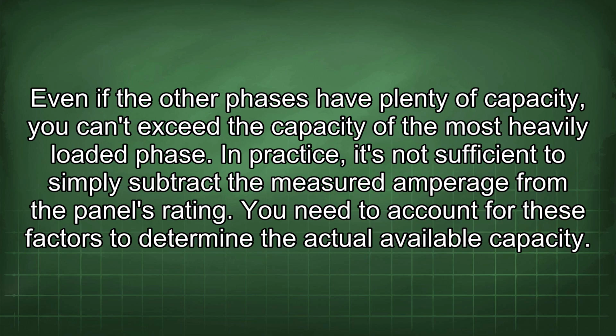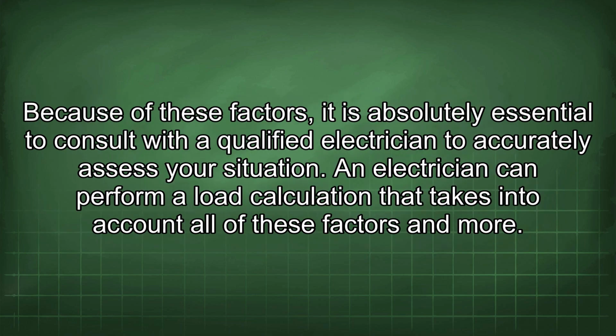In practice, it's not sufficient to simply subtract the measured amperage from the panel's rating. You need to account for these factors to determine the actual available capacity. Because of these factors, it is absolutely essential to consult with a qualified electrician to accurately assess your situation. An electrician can perform a load calculation that takes into account all of these factors and more.